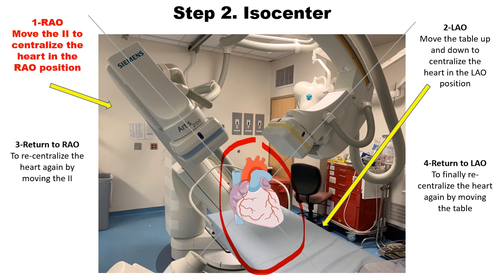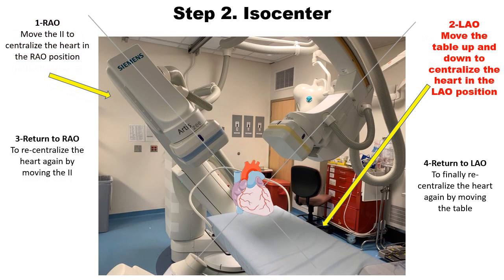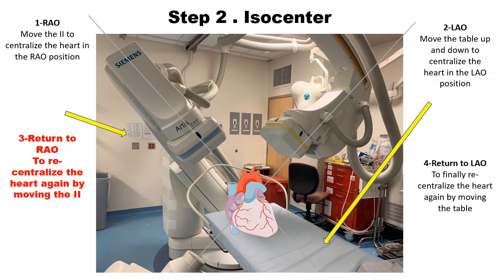The way we do it is we start in the RAO position. We move this image intensifier until we get the heart centralized in the RAO position. We then want to centralize the heart in the LAO position, and the way we do that is by moving the table up and down — not by moving the image intensifier at all. This is followed by returning to the RAO position to re-centralize the heart again by moving this image intensifier.